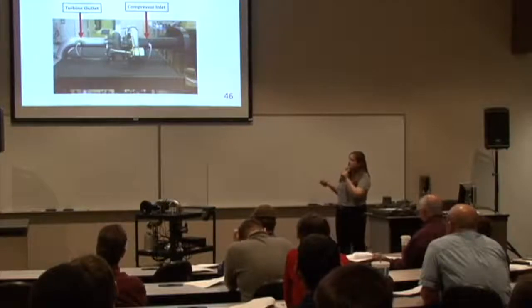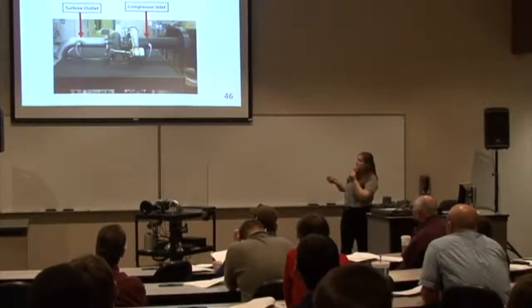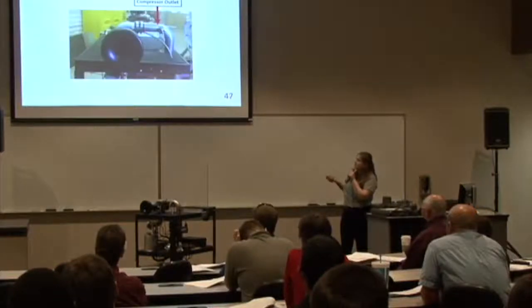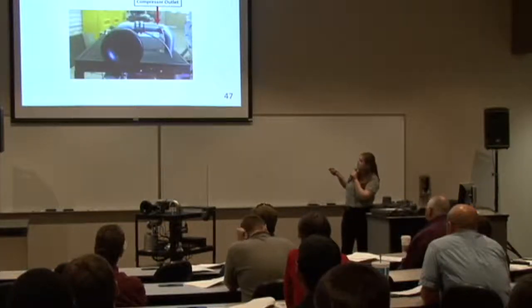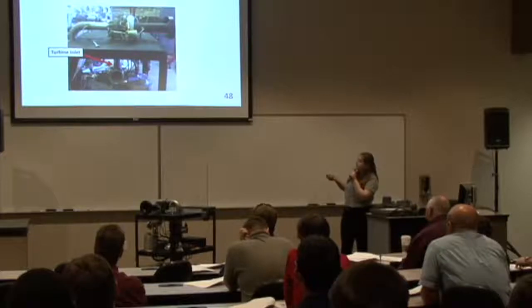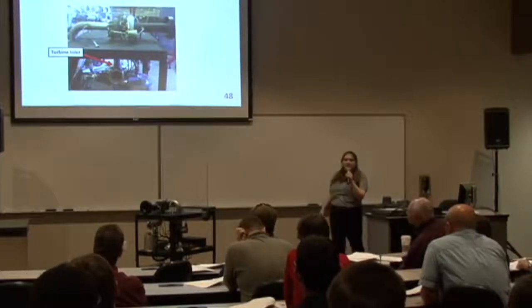In this picture, you can see the pitot-static tube is installed on the turbine outlet side and also on the compressor inlet side. It's also been installed into the compressor outlet and over here on the turbine inlet. At each one of these locations, we are getting a total and static pressure measurement.